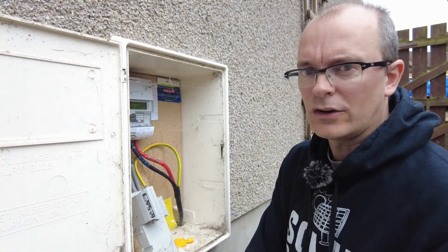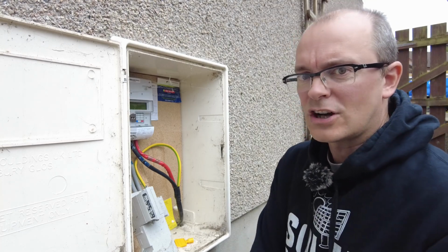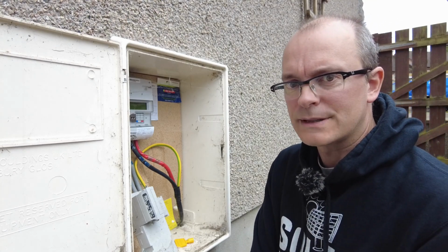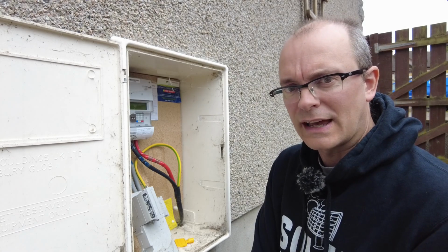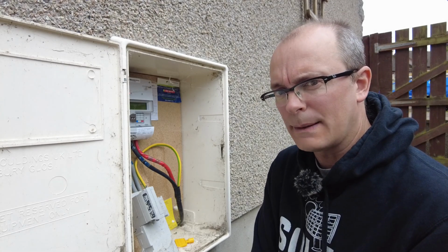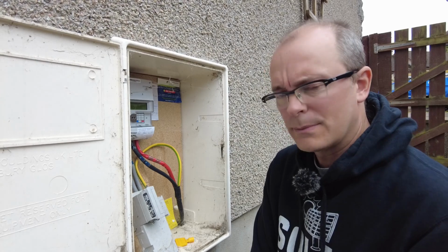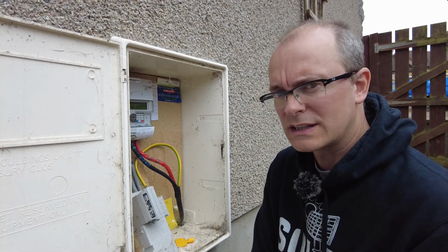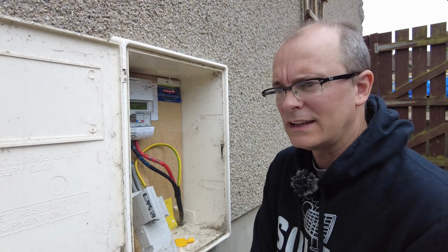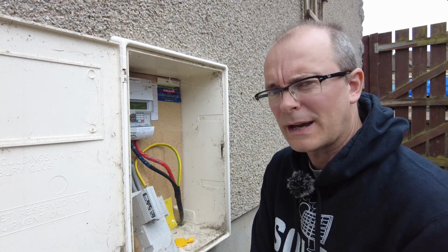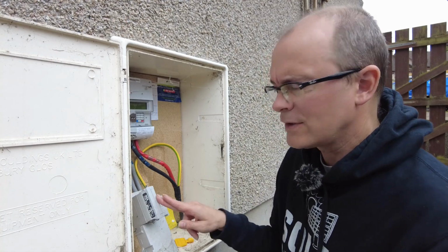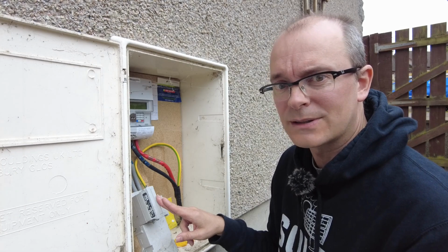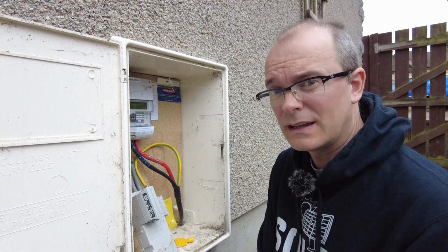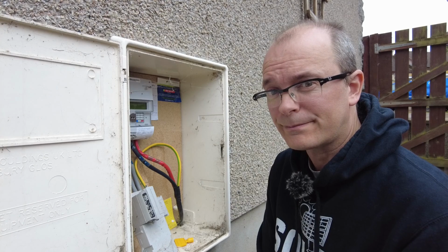Now, consider that on the Octopus Go tariff, you're charging up a car at 32 amps. You're charging up your SolarEdge home battery at 21 amps. You're charging up potentially the hot water cylinder at 13 amps. And then you've got 1 amp of base load. You're at about 67 amps. And if this fuse in here is only rated at 60 amps, then after a period of time, the fuse is going to blow.